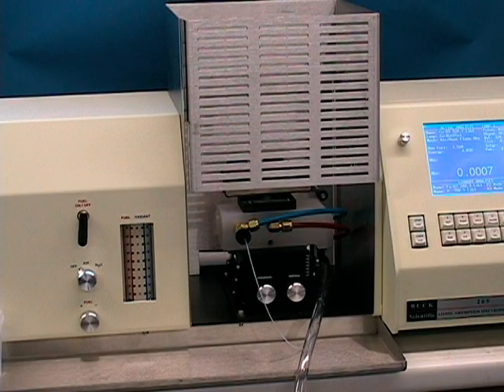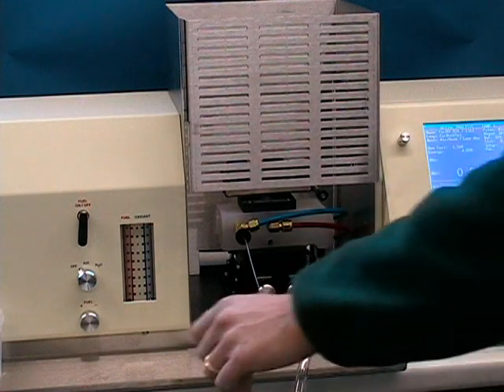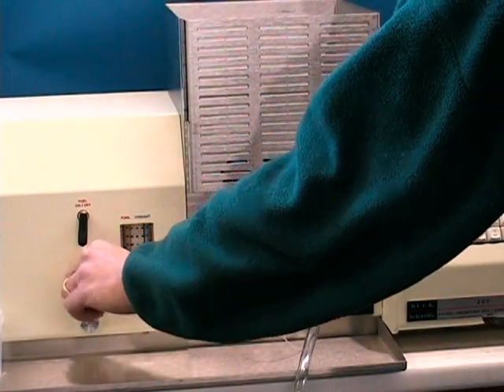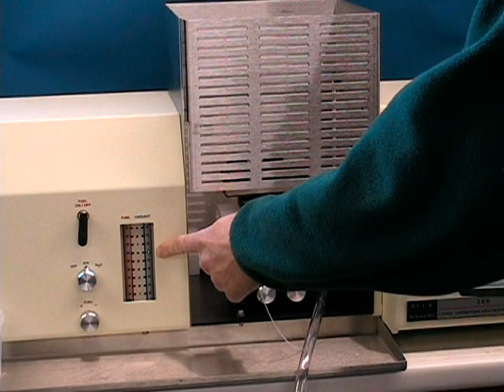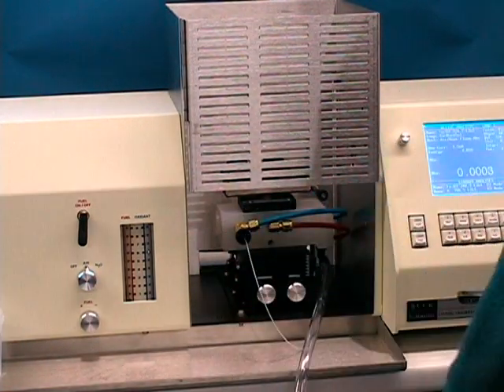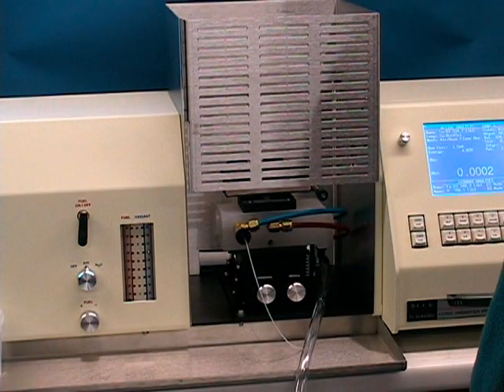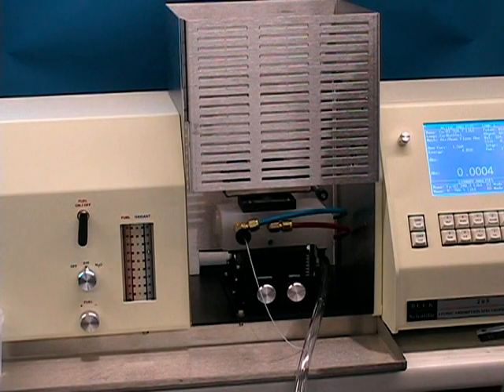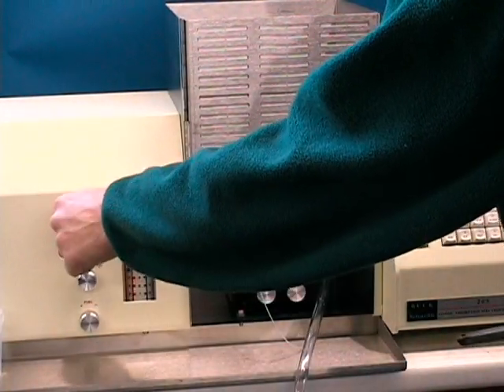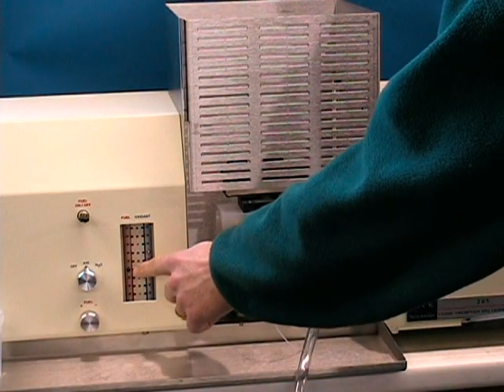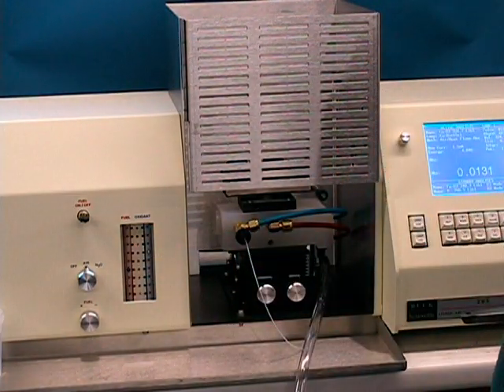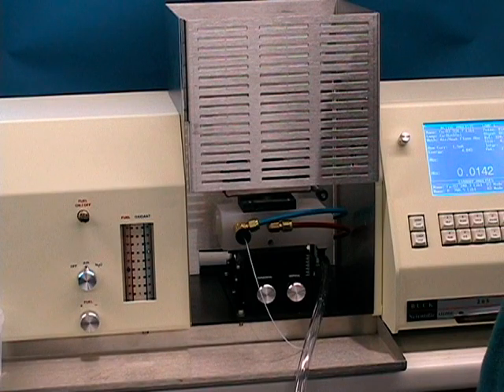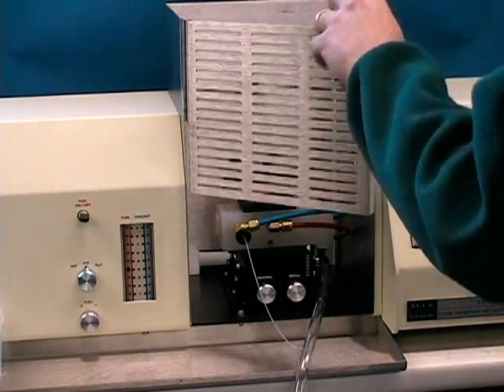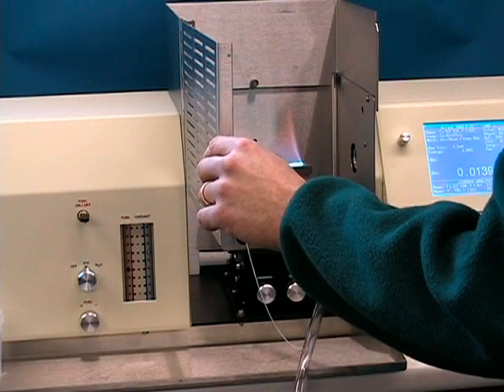Make sure that your gas tank valves are open and your regulators are properly set to the required pressures. Rotate the valve for the air from off to air, and you will see a float appear in the flow meter. The airflow should be somewhere in the middle, anywhere between 4 and 7. At this point, turn on your acetylene valve, and again you will see the float for the flow meter for the acetylene approximately 1 or 2 units less than the setting for air. At this point, open your burner shield and ignite the flame.